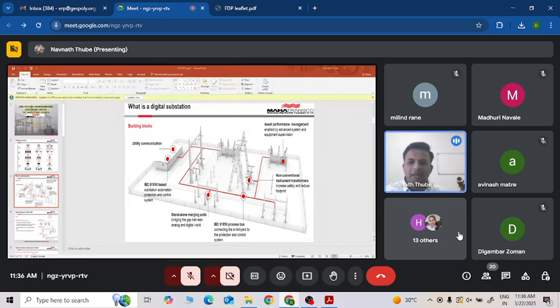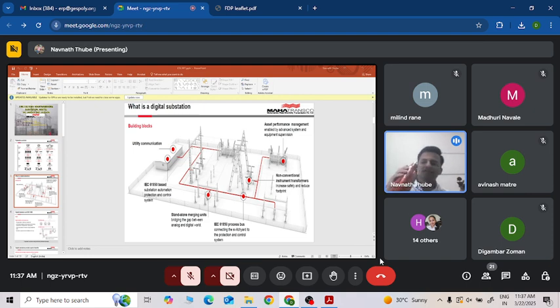In the PIB, the details about the SAM unit are as follows. SAM600 process bus input output system, stand-alone merging unit. Bridging the gap between analog and digital technologies, the SAM modular process bus input output system is placed in the field to connect conventional equipment to the IEC 61850 process bus. High accuracy for revenue metering while covering the whole dynamic range of protection. Fast data acquisition and communication for time critical protection applications. Modules for various processes: current measurement, voltage measurement, time synchronization, and scalable input-output binary signals. This SAM unit is important in a digital substation.